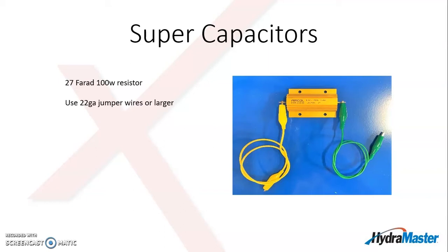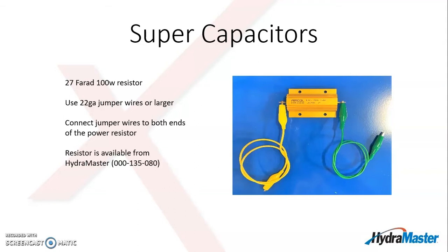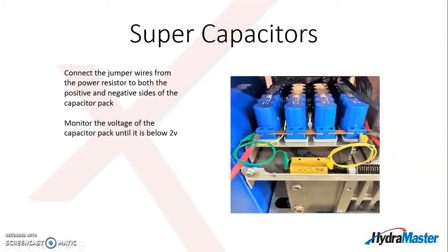So you just put a couple of jumper wires, one on either end of the resistor, connect those jumper wires to the positive and negative sides of the capacitor pack, and this resistor is available from HydraMaster as part number 000-135-080. So connect the jumper wires from the power resistor to both sides of the capacitor pack, the positive and negative, as shown in this image here. And then monitor the voltage, either with the gauge or with the multimeter, until the voltage on the capacitor pack is down below 2 volts.